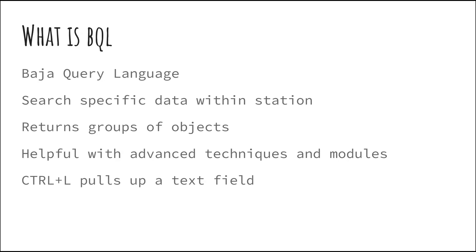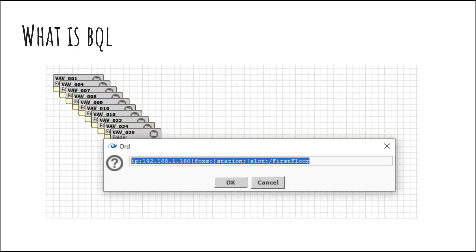At any point in time in Niagara within the station, you can use Control+L to pull up a text field that allows you to navigate to any manually input ORD, which stands for Object Resolution Descriptor — an internal Niagara URL. These ORDs are what you get when you copy an individual component inside of a station. Here we can see I have a floor with VAVs under it, and hitting Control+L brings me up to this particular ORD.